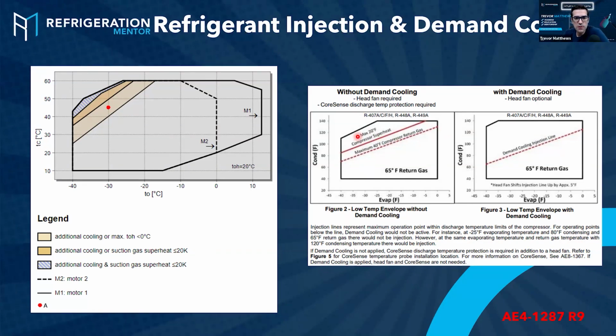I work in refrigerant transport with open compressors, and it's common to see 52 Celsius TC, and a maximum can be lowered. The TE minus 25C and works perfectly without liquid injection. Excellent. So that's fine. You just want to make sure that that oil doesn't get too hot. What is that discharge temperature? You've got to be monitoring that. What type of compressor are you using? Are you using an open drive compressor versus a semi-hermetic or a scroll compressor, right? So there's a lot of differences in that, depending on the compressor design. So thank you for letting us know, Hector, on that.